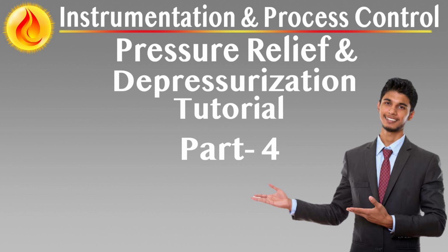Effects of simultaneous operation of multiple depressuring valves. If validated dynamic modeling tools are used, designers may take credit for pressure equalization and staged flow, which can reduce the required pipe diameter or flare tip size.